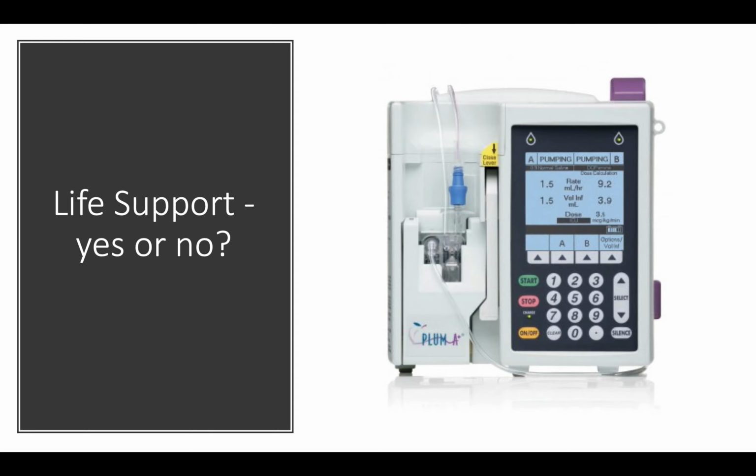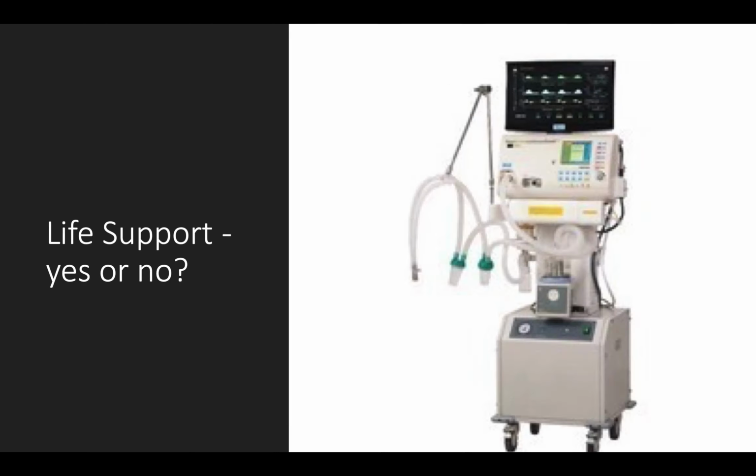Well, typically, no, this is not going to be used for life support. If this fails, yes, the patient may not get the medicine that they need, but there's ways that we can work around that. If it fails, typically we get an alarm and we'd have time to provide any medications that would be needed to the patient. So no, this would not be considered life support equipment.